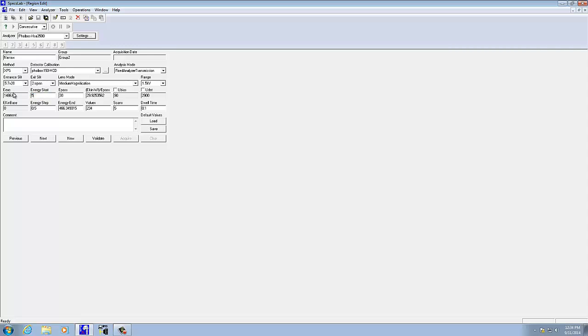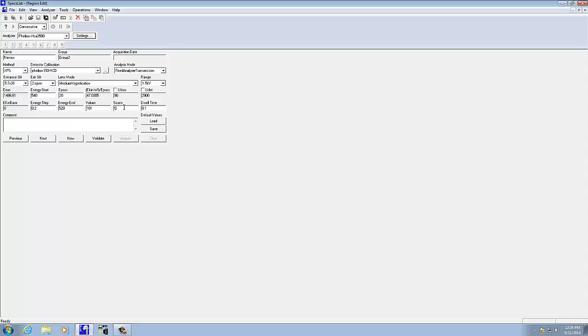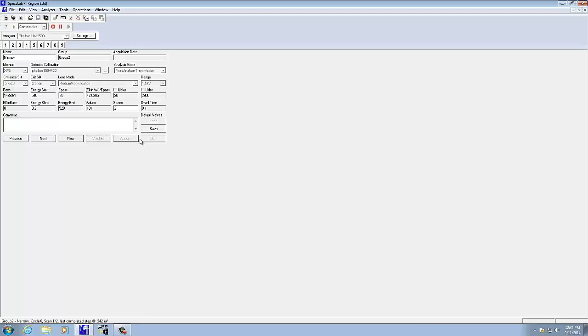I'm going to go from 540 EV to 520 EV, and let's change the pass energy to 20 EV, and we'll go to 0.2 for the step size. Depending on the number of scans, let's just do 2 here. After all that's entered, we hit validate, and then acquire.